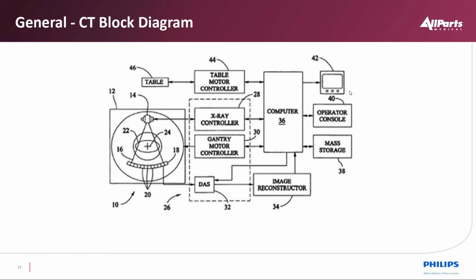The operator's console is running the main computer that reaches out to all these other controllers to drive them. So we'll be spinning the gantry and also driving the table through at a given rate, so we're building a volumetric cylinder up. And then the mass storage at the end of the computer holds a DICOM image that will later be copied, transmitted by DICOM to a DICOM server.